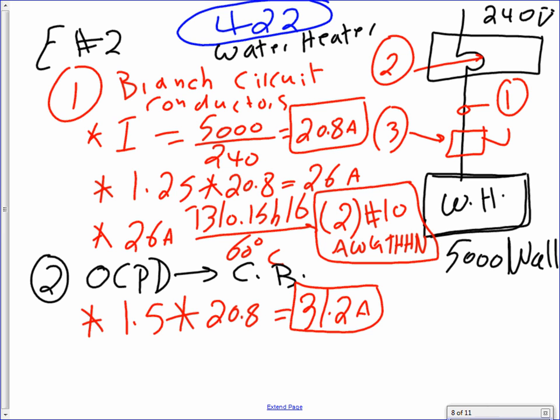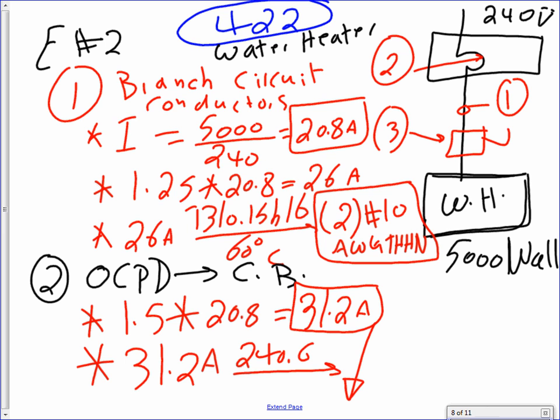Then you take the 31.2 amps and take it to 240.6, and go down, though you are allowed to go up to 30 amps. So I have my 30 amp circuit breaker protecting the heater. Can number 10 be protected by 30 amps on a heater? Yep. For a heater, yep.